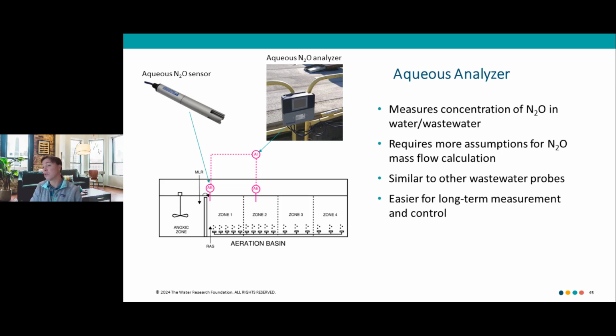The probes themselves and the controller are fairly similar to other wastewater probes. It looks pretty similar to a DO or pH probe with a controller, like something from Hach or YSI. So there's a familiarity there. You can integrate it into your SCADA system and have it do internal calculations to spit out emission estimates if you feed it airflows. We did all that post-processing to make the installation real simple. But we do definitely see it as easier for long-term measurement. It doesn't take a ton of calibration, and it could be integrated into controls in the long term.